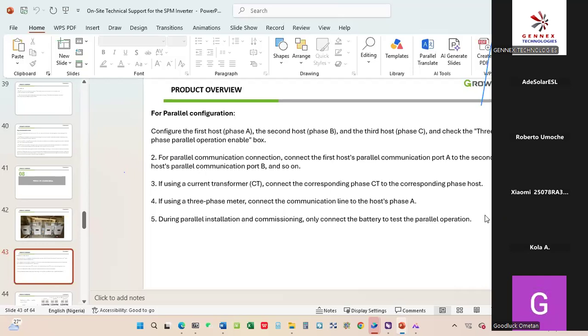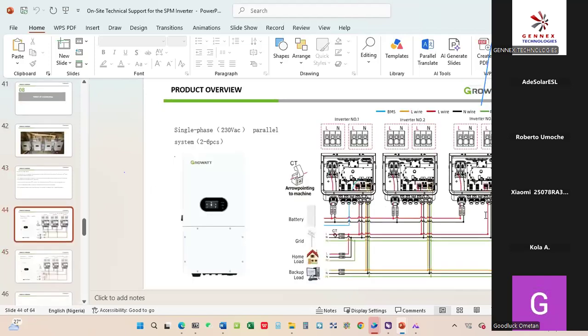And also connect the communication cable between the inverters. For the first inverter it is out, and for the second inverter it is in. You connect them according to the number of inverters you have, out to in, out to in, up to your last inverter. In a single phase mode, this inverter you can connect up to 6. Then in a parallel mode, you can connect up to 3.